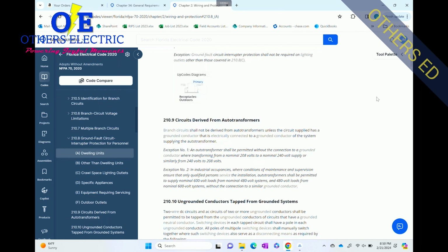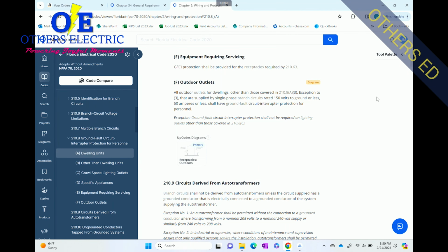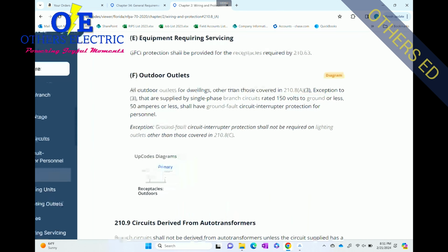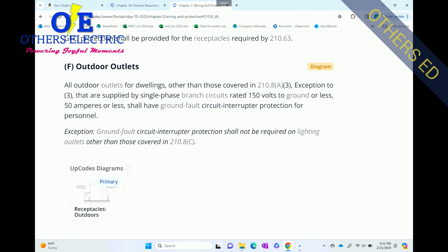210.8F of the 2020 NEC, National Electrical Code. It says here that all outdoor outlets for dwelling units other than those covered in 210.8A3, exception to 3, that are supplied by single-phase branch circuits rated 150 volts to ground or less, 50 amps or less, shall have ground fault circuit interruption protection for personnel.